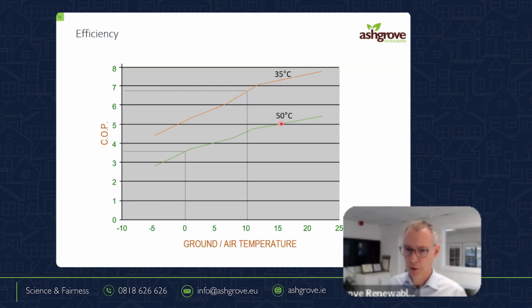No, by the way, 5 is not bad. But again, as the outside air temperature or the ground temperature drops, you're down now to 3. So these things are within our control. That's a graph. We've taken those figures from a Swedish heat pump, Thermia, and we just transposed it onto a graph like that. So if we're putting pipes into the ground outside, we'll say we need a kilometre of pipes buried in a field or in wells.